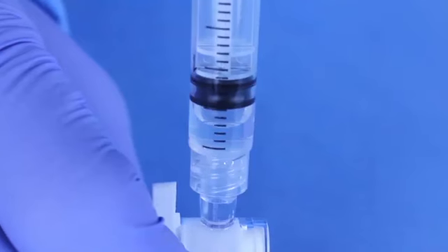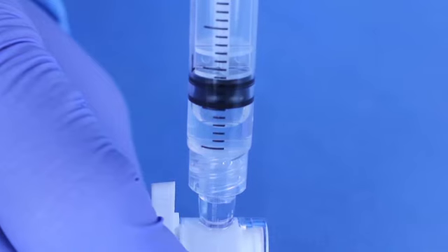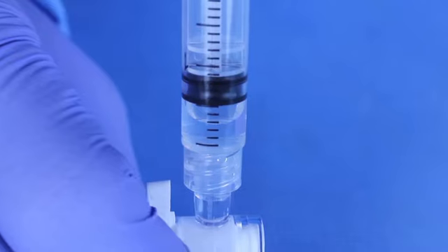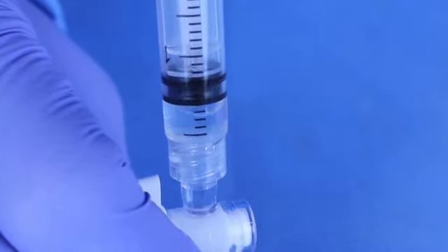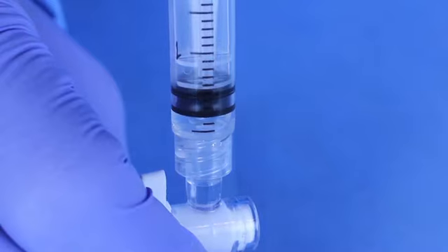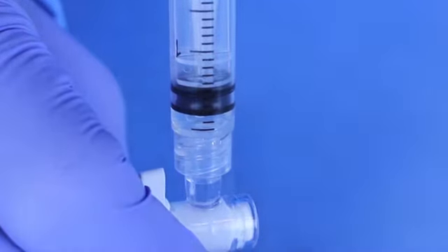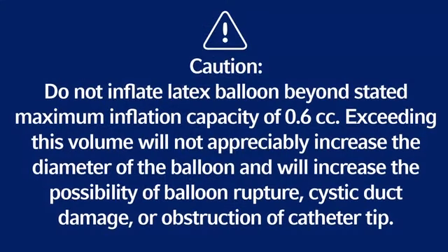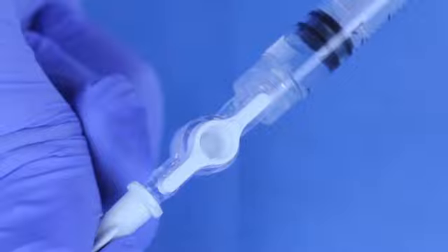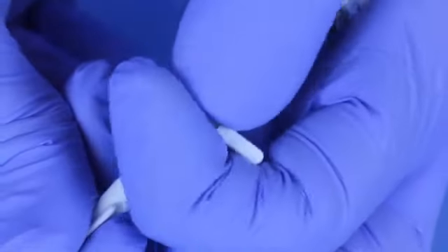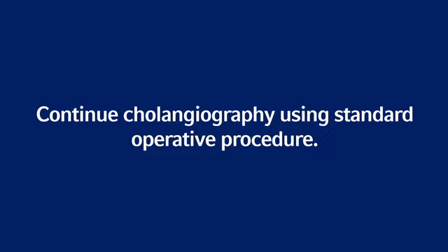When catheter is positioned in the cystic duct, note fluid level on syringe barrel. Inject 0.1 to 0.2 cc of fluid to inflate balloon approximately 6 mm in diameter. For larger cystic ducts, up to 0.6 cc may be used for balloon inflation. Maximum balloon diameter is 8 to 10 mm. Caution: do not inflate latex balloon beyond stated maximum inflation capacity of 0.6 cc. Exceeding this volume will not appreciably increase the diameter of the balloon and will increase the possibility of balloon rupture, cystic duct damage, or obstruction of catheter tip. Turn stopcock lever perpendicular to catheter to maintain balloon inflation. Continue cholangiography using standard operative procedure.